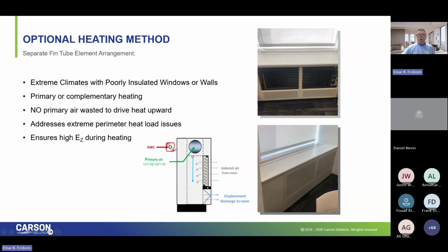So as an alternative mechanism to heating, we can implement fin tube radiation. We deepen the coil by about 3 inches. We have 2 rows of fin tube radiation. We have inlet grills in our toe kick area, as well as multiple paths along the side of the coil for that room air to get back to the heating elements to deliver that warm, buoyant air to address the direct fenestration loss. And that's really the engineer's call. I would say that we do maybe 1 or 2 of these designs with the fin tube integrated. It's really an engineer's call whether they feel they need the added protection based upon envelope design.